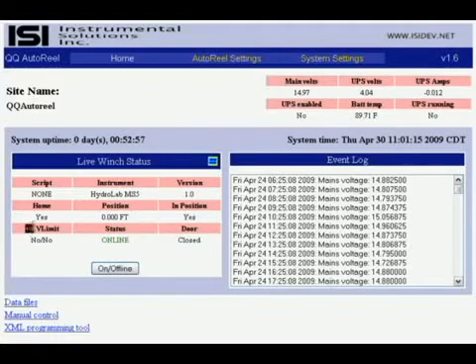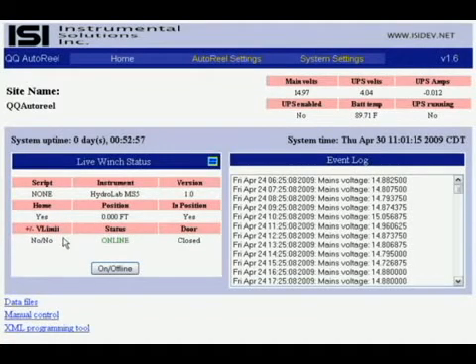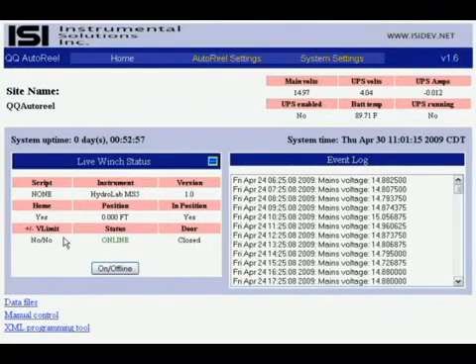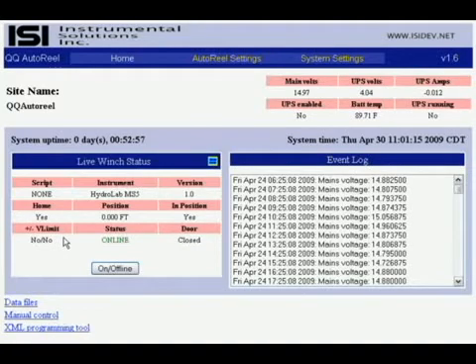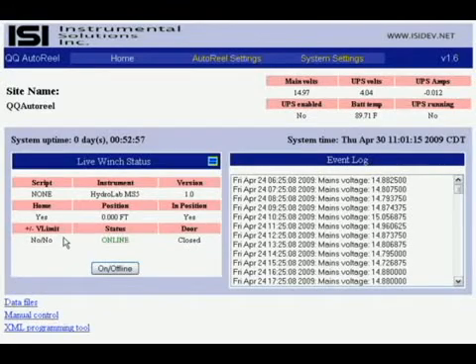Virtual limit - are either the positive or negative virtual limits in effect? No. You define a parameter in this system, which is maximum cable length. If you were to define, say, a maximum cable length of 10 meters and then attempt to pay out 12 meters of cable, at 10 meters you would activate the virtual limit switch, and it wouldn't pay out past that.